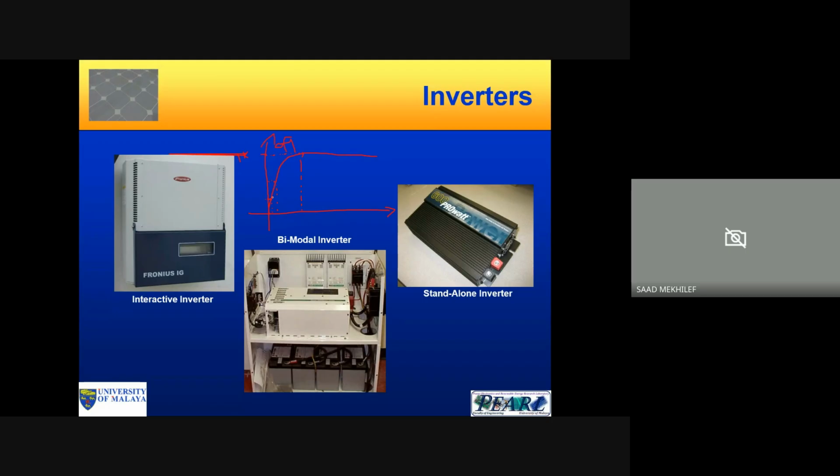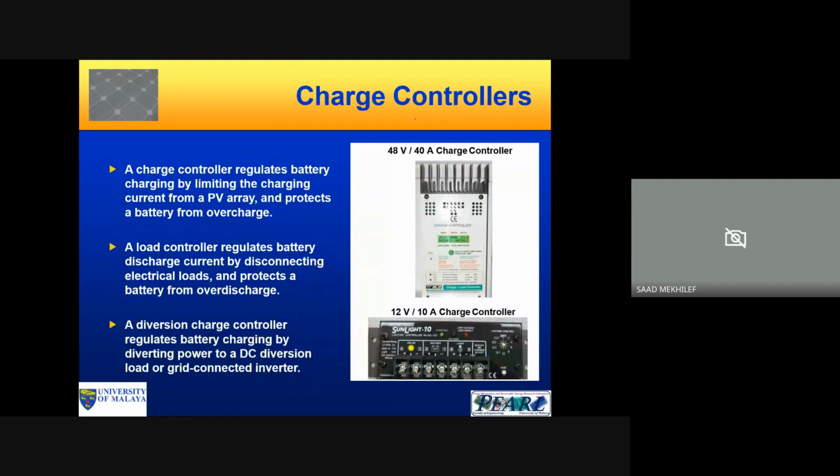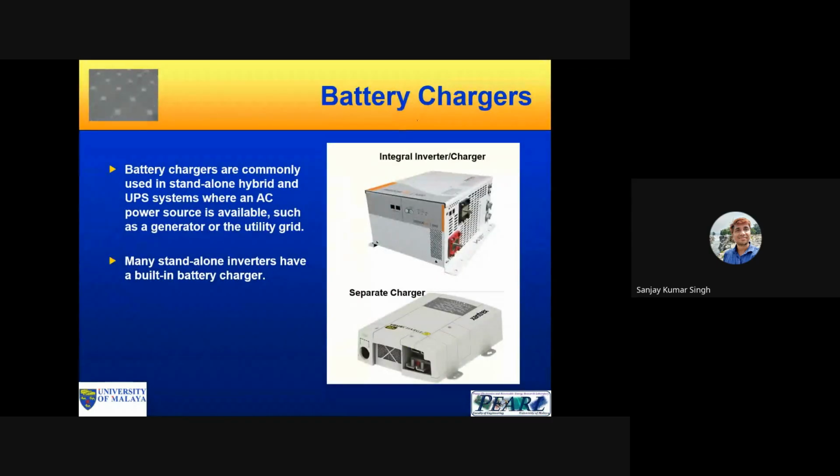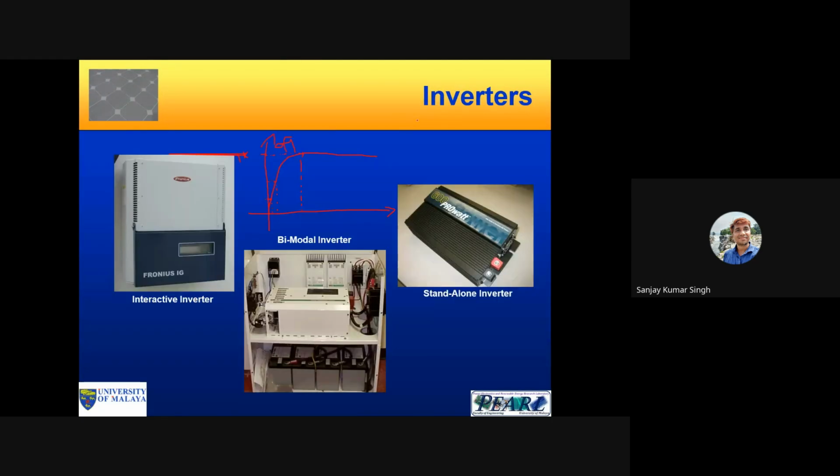So to make sure the inverter matches the power produced, we have to derate it by 20 to 30%. We can even go to 700 watts. We will demonstrate this, do some calculations, and I will show you why we have to derate. Any questions?